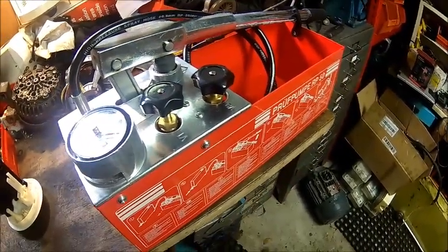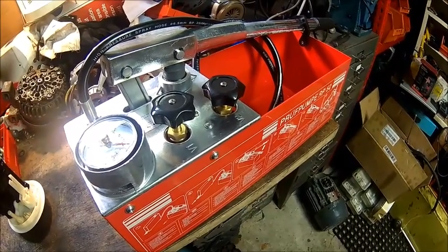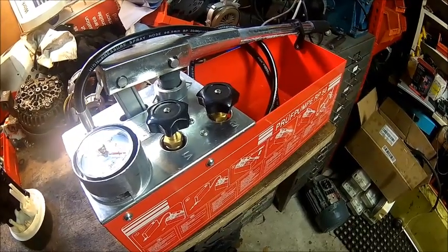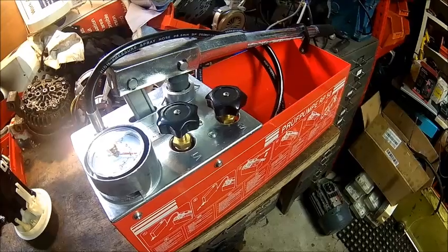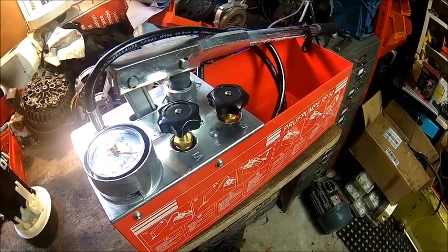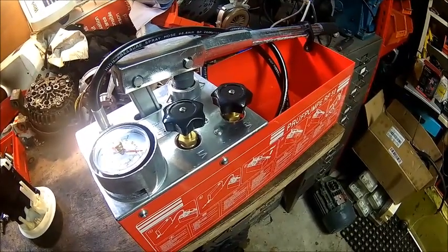We give that a try because we need to test one of our compressors. It was sitting for several years and I don't have the balls to turn it on because I don't know how the vessel is. So we're going to test that. What you do is you don't test them with air — you test it with water. And if it pops, only the water comes out. It doesn't explode. That's the principle.